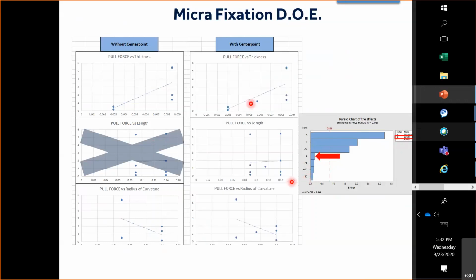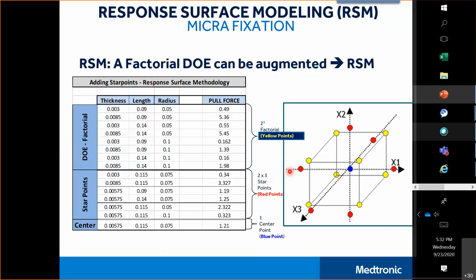And the center point, you see, does not fit on the line, so we could not go with a linear model. If we wanted a good model for how fixation force went with thickness and radius of curvature, we needed something more than a linear function. The way to get more than a linear function is an extension of design of experiments called response surface modeling, abbreviated RSM. So we added additional star points. We augmented those first 8 runs of the DOE to make it a response surface design. We added that center point I mentioned, and then 6 star points, represented over here with these 6 red circles. The center point is a blue circle, and the original DOE runs are shown with these little yellow circles at the corners of the cube of the 2 to the 3rd factorial design. So now we can reanalyze this and get a quadratic equation, a polynomial.